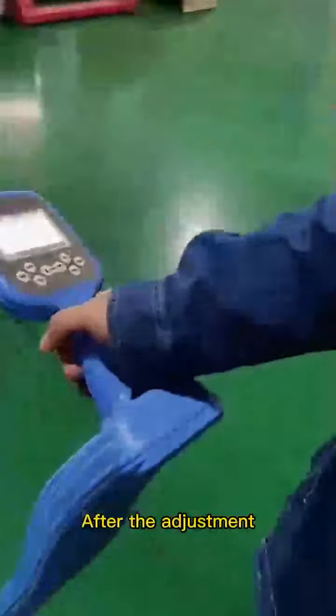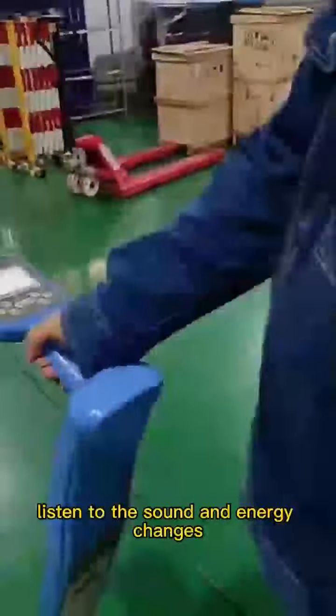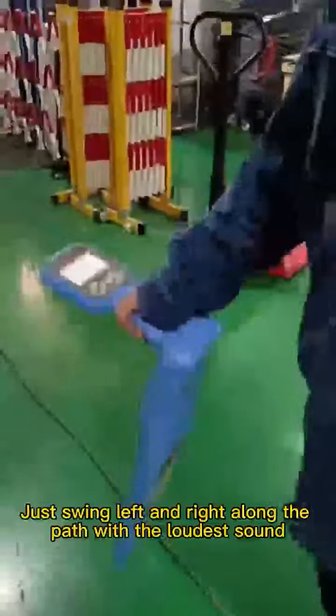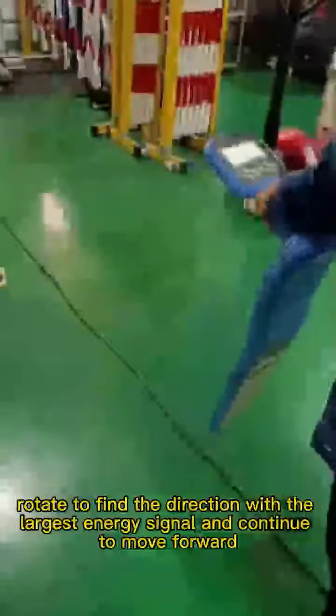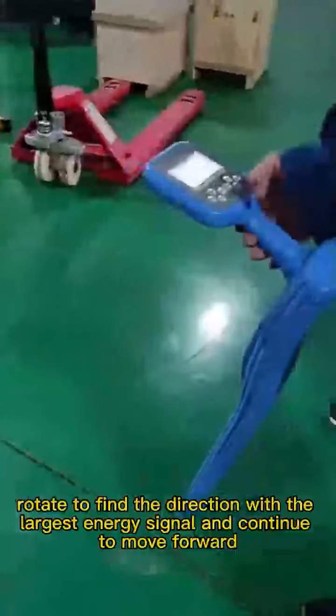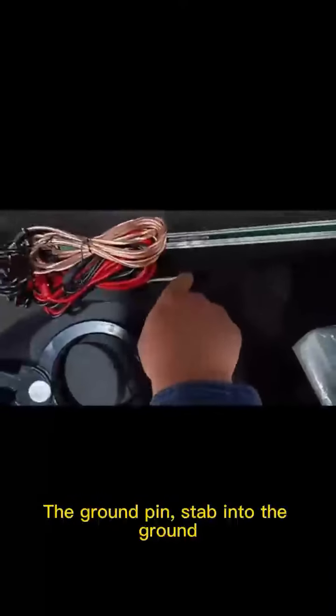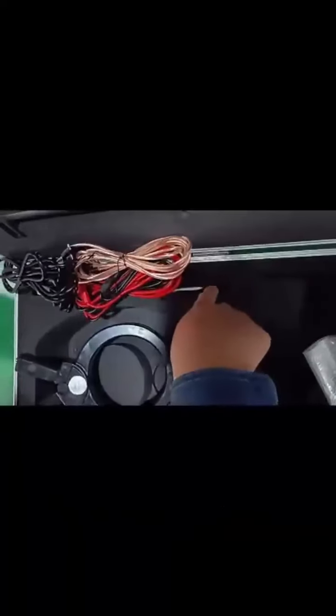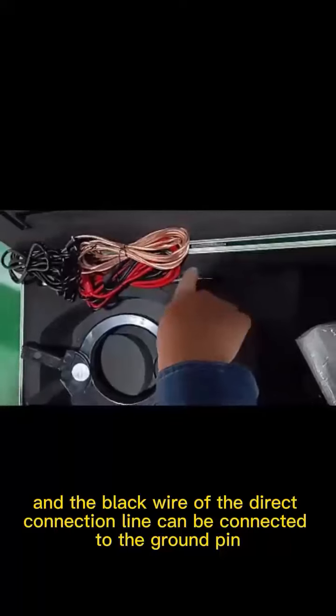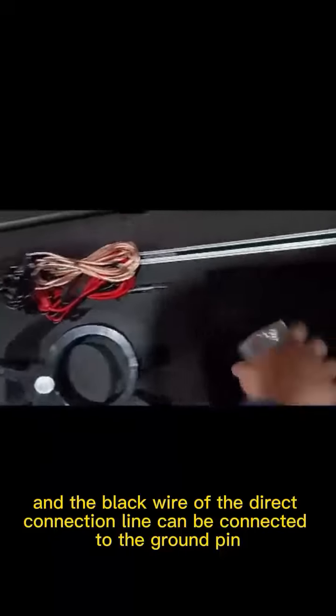After the adjustment, keep the gain value unchanged. Listen to the sound and energy changes, and keep moving forward. Just swing left and right along the path with the loudest sound. If there is a turning point, rotate to find the direction with the largest energy signal and continue to move forward. The ground pin, stab into the ground, and the black wire of the direct connection line can be connected to the ground pin.